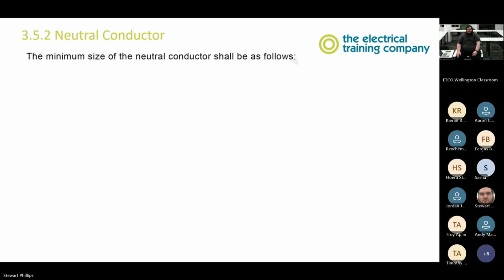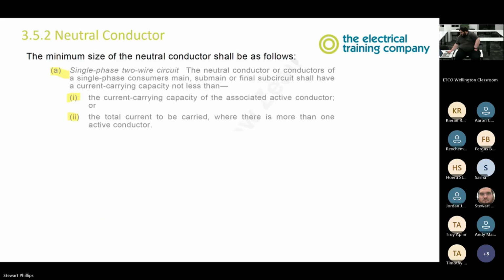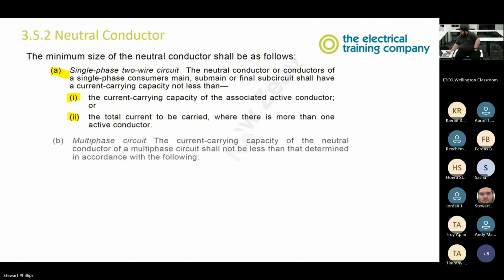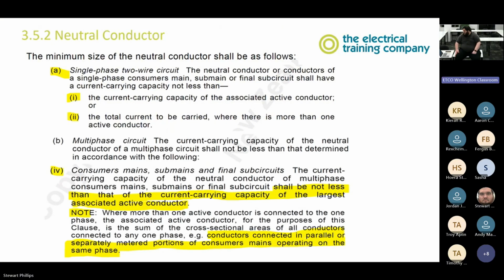Cool. Minimum size of the neutral conductor. So it should not be less than that of the current carrying capacity of the largest associated active conductor. So if we have a 25 mil phase, we must have a 25 mil neutral. Even if, for example, we've got 3 phases running to a property, one of them is 25, 2 of them are 16, our neutral conductor must be 25 because it must match the current carrying capacity of the largest associated active conductor.